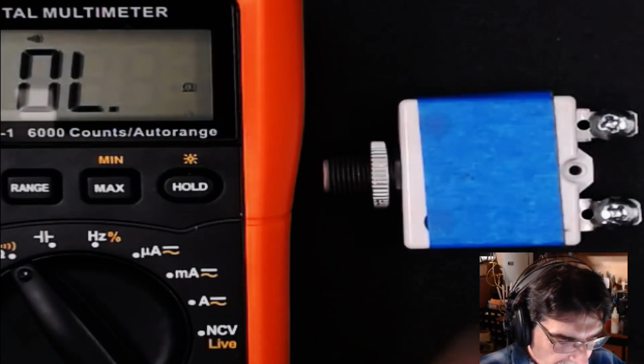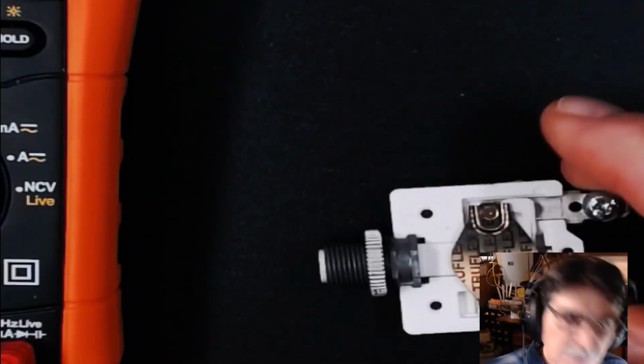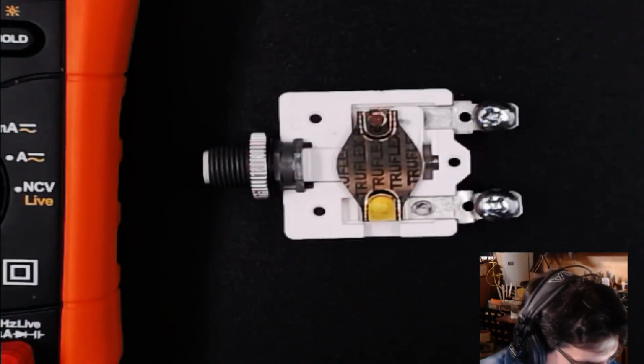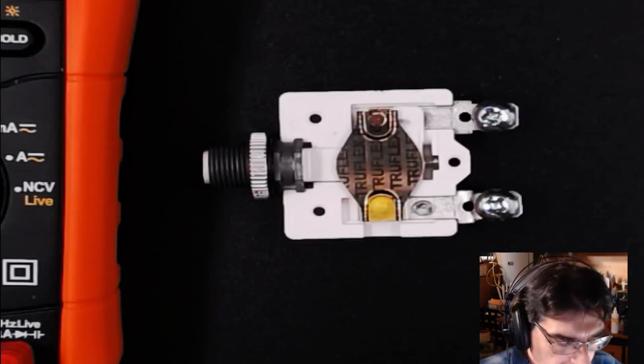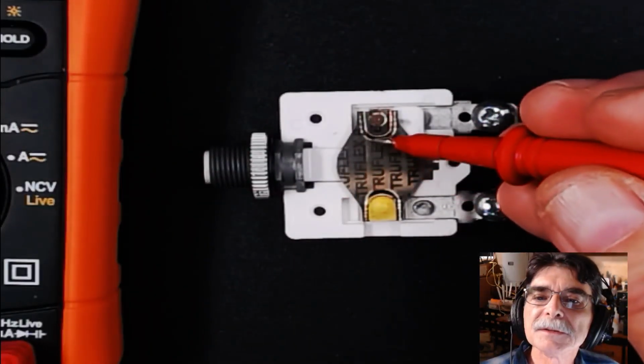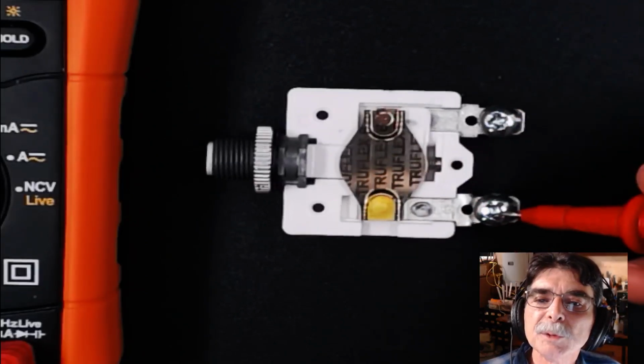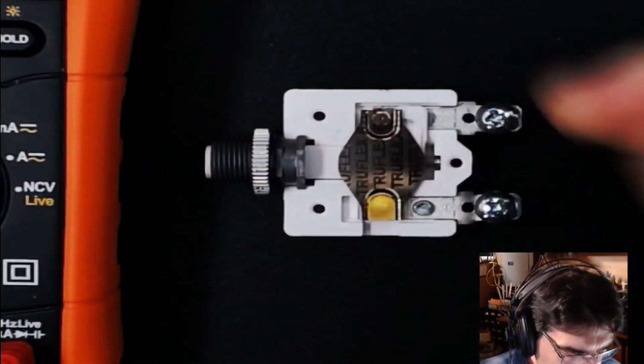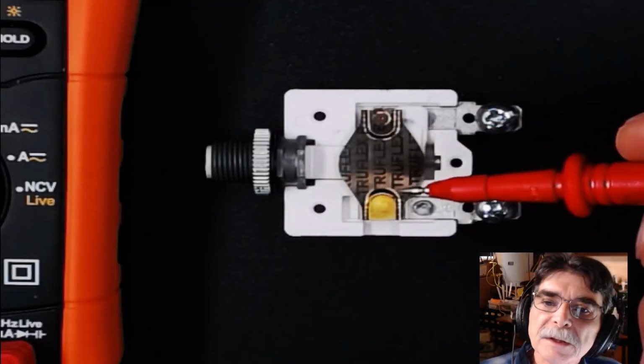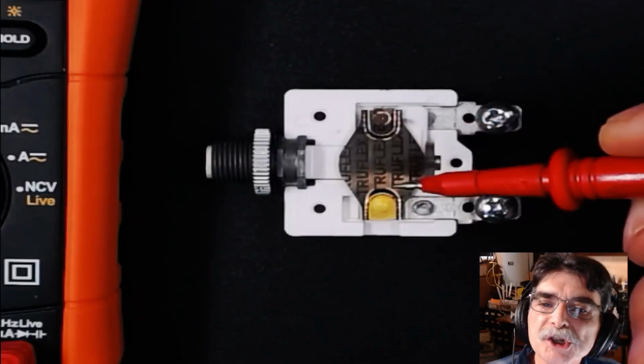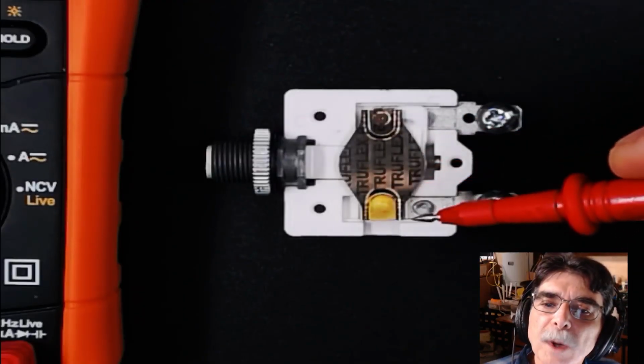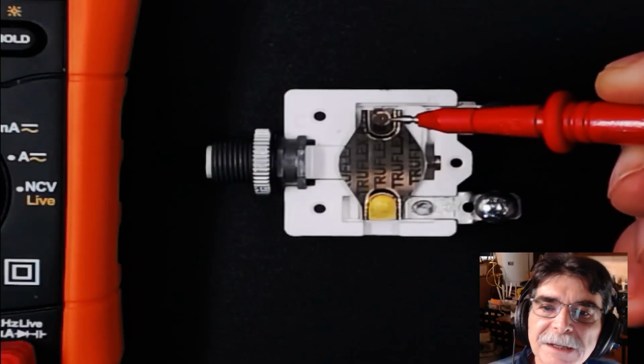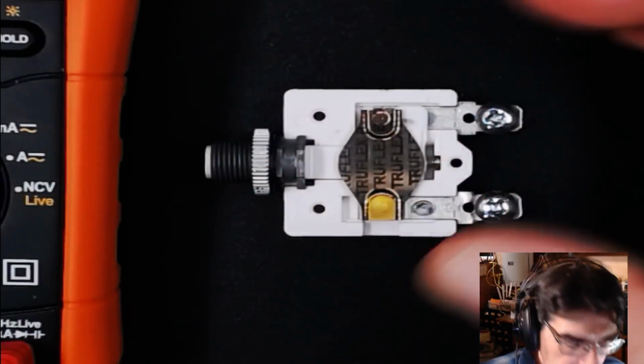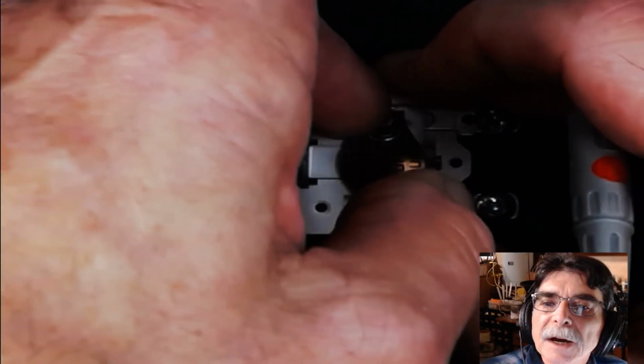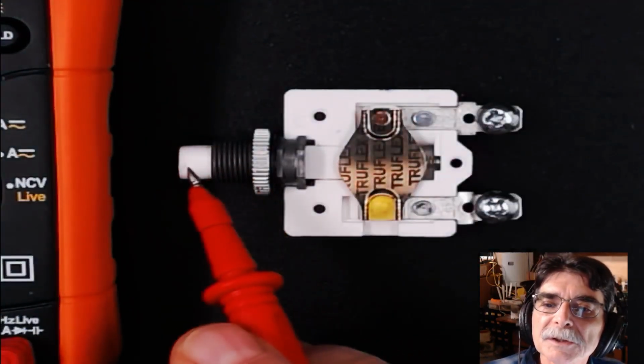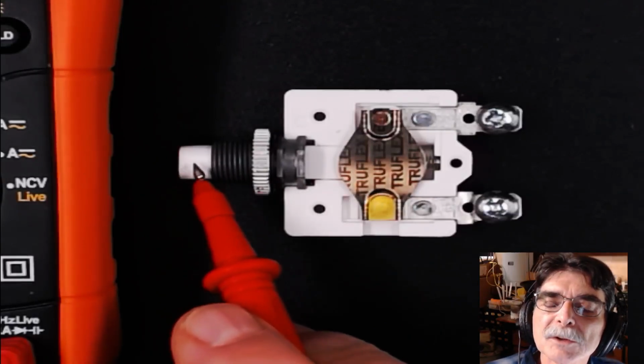And here's something cool that you don't see often. This is what it looks like inside. A circuit breaker has what's called a bimetallic element in it. This piece of metal between the two contacts is bimetallic, and what it does is change shape as it heats up. So when current flows through this circuit breaker and exceeds the value, in this case 15 amps, it trips. I'm going to manually trip it by pulling up on the contact. Look at this section. You see how much farther it's sticking out?